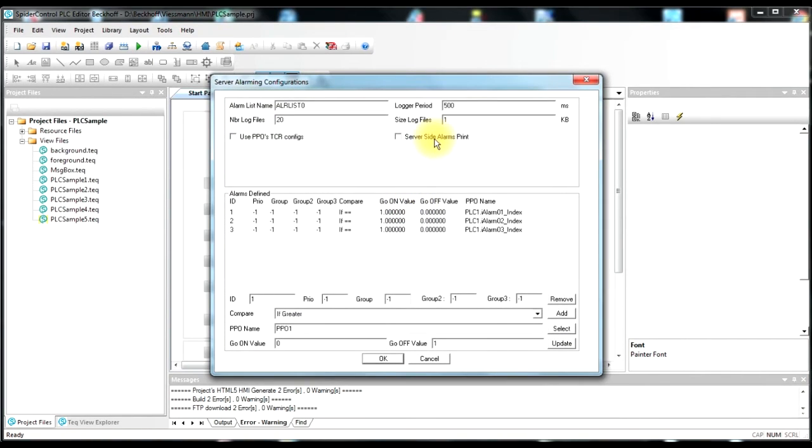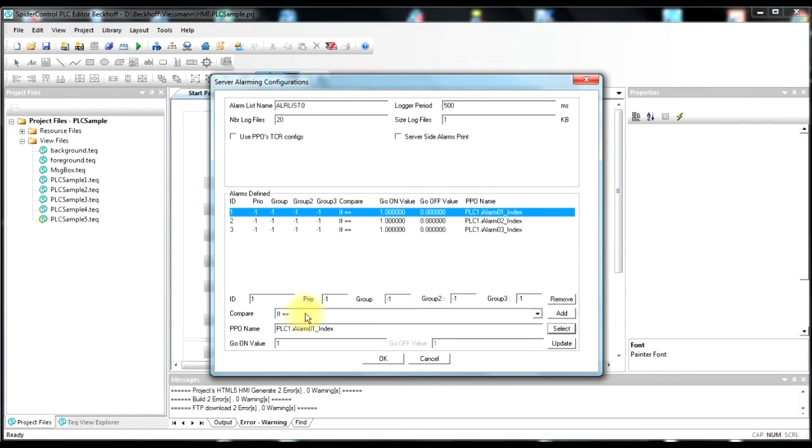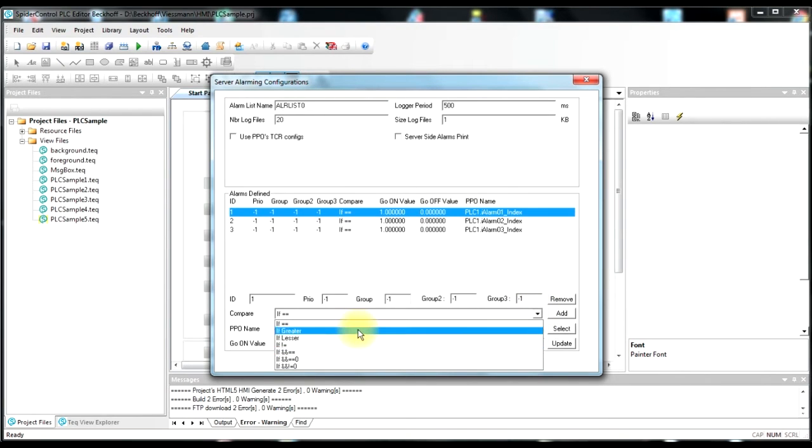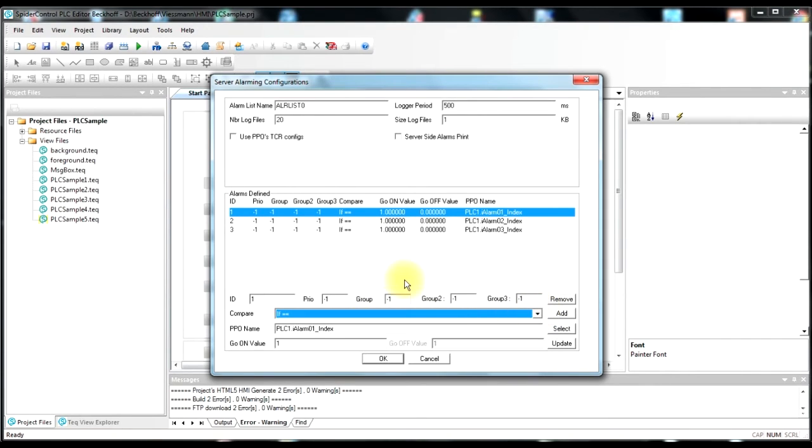We begin with alarm configuration. So alarm configuration is done by choosing the respective variable from the PLC, adding a condition for which the alarm will be active. Every alarm has its own alarm ID, so it starts with 1, 2, 3, etc. We can add a condition when it goes on and when it goes off. And a condition can test on bits or can compare if a value is greater or lesser and so on.